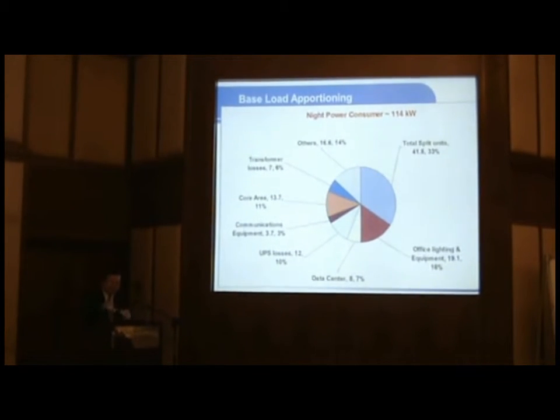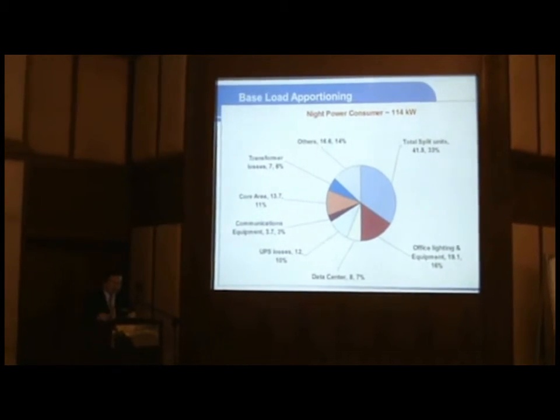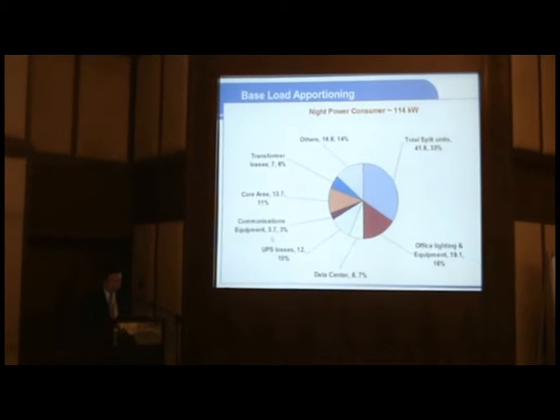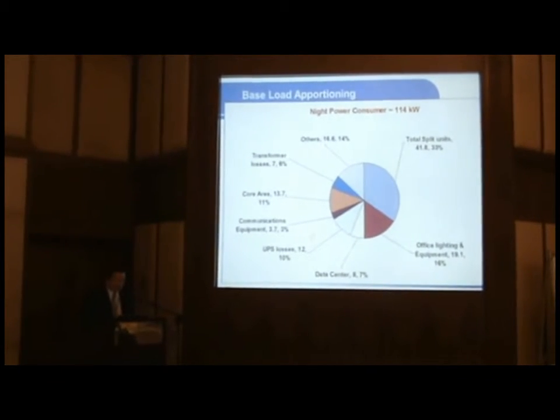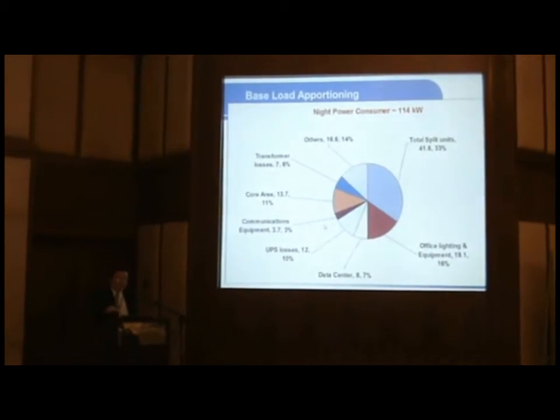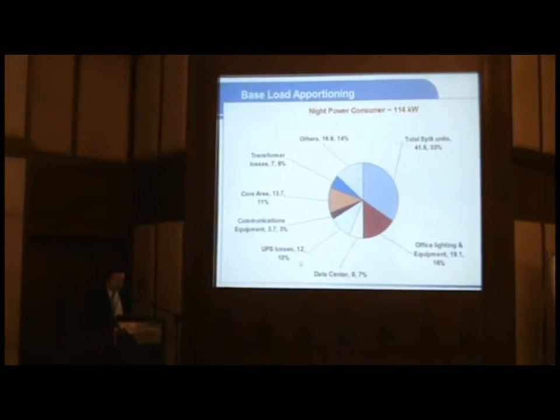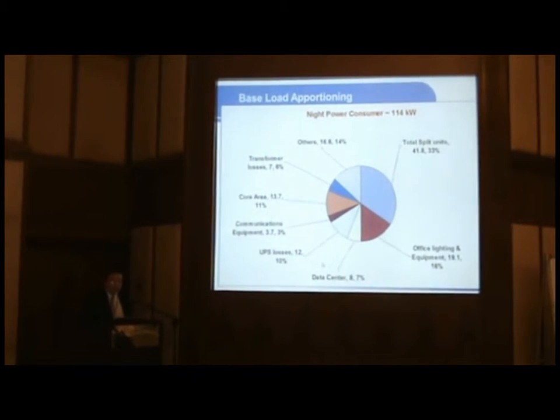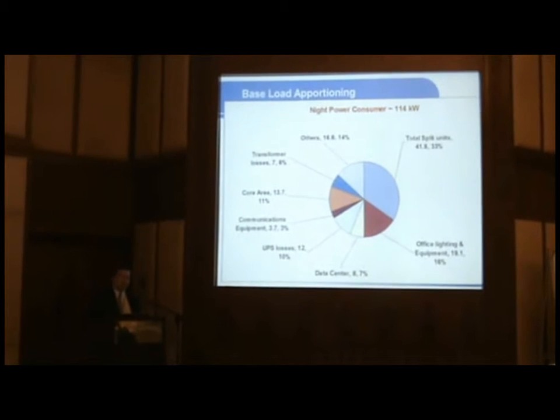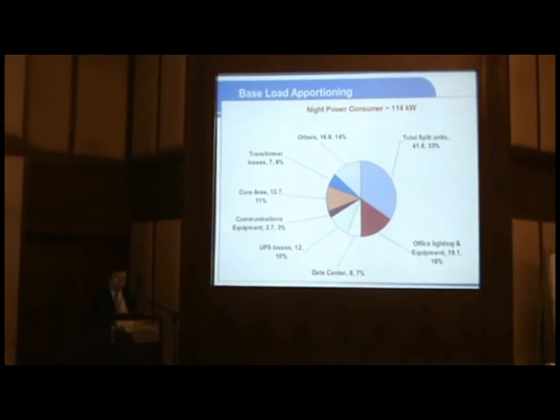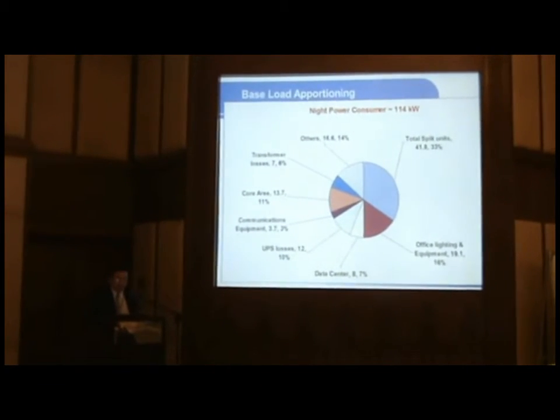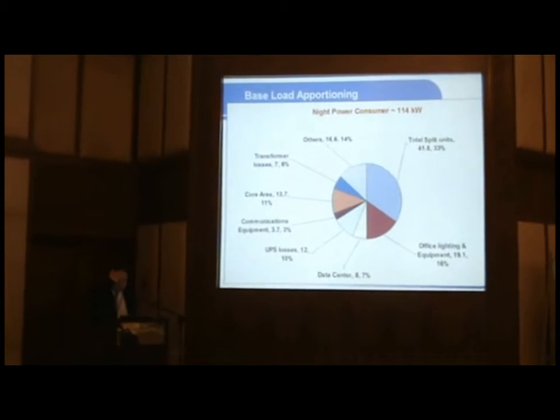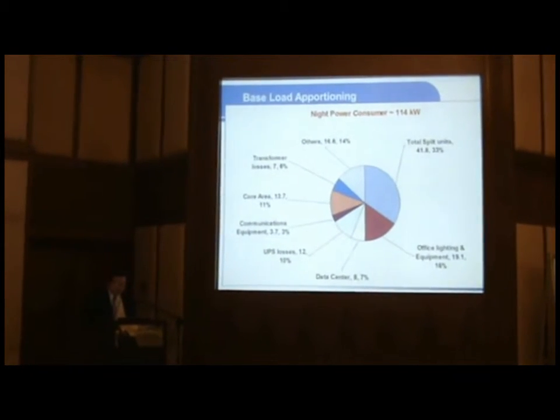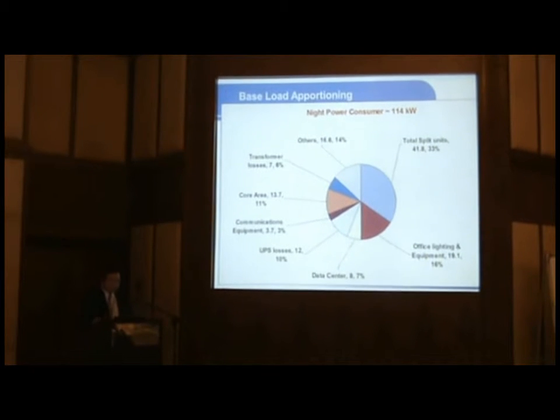The core area is where part of the ICT hub and switches sit, because the meter power supply is together with the lighting in the core area, running 24 hours. Communication includes the Cellcom and Maxis servers also inside the building. UPS also has high losses; the reason is the capacity of UPS is higher than the consumption, because the building already has low energy office appliances, but the UPS provided is higher.